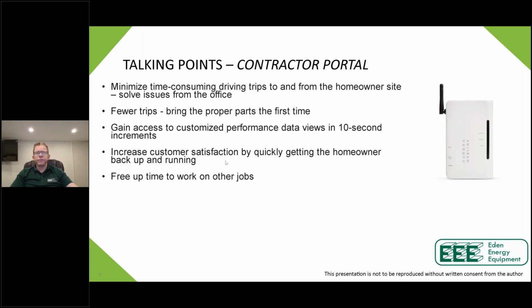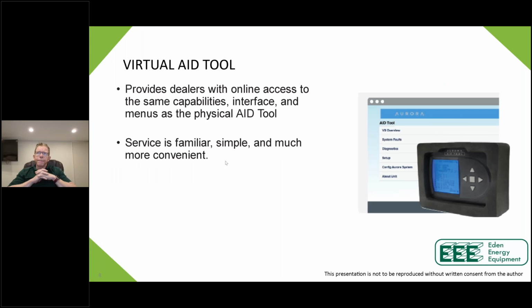Yeah, I think other than just having the remote accessibility, which is nice on a whole lot of levels, I think of specific instances, one I've never forgotten, where we kept having a heat pump lockout on freeze protection. And no one could figure it out because you go to site, it works, right? The heat pump performs, everything's great. You ohm out the thermistor, it looks good. Refrigeration's good, loop's good, ethanol concentration is good. There was absolutely no reason for this heat pump to be locking out. And then we finally got on and started going through the weeds on the web link. And we might have had to actually add the Symphony after the fact.